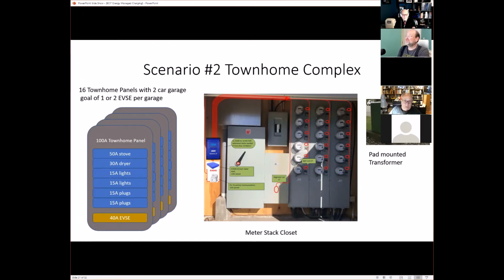We would have one EV EMS computer and one of the DENT meters installed in the meter stack closet, and we would monitor everybody's load, just like BC Hydro does, so we could protect the pad mounted transformer.